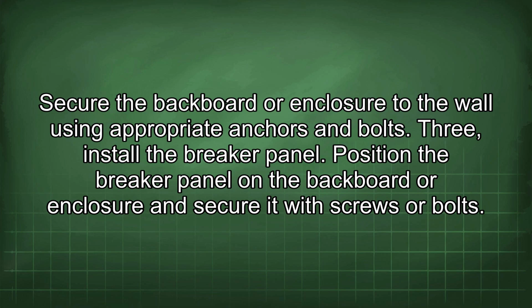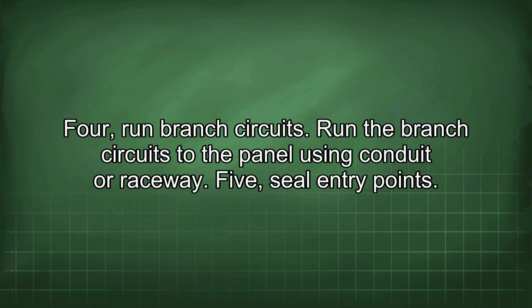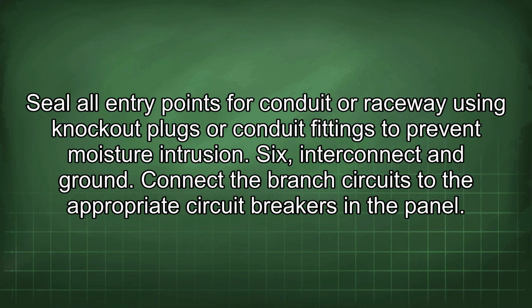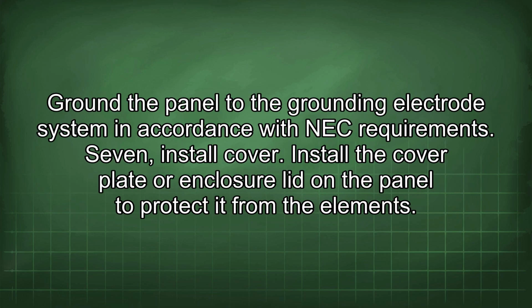3. Install the breaker panel. Position the breaker panel on the backboard or enclosure and secure it with screws or bolts. 4. Run branch circuits. Run the branch circuits to the panel using conduit or raceway. 5. Seal entry points. Seal all entry points for conduit or raceway using knockout plugs or conduit fittings to prevent moisture intrusion. 6. Interconnect and ground. Connect the branch circuits to the appropriate circuit breakers in the panel. Ground the panel to the grounding electrode system in accordance with NEC requirements. 7. Install cover. Install the cover plate or enclosure lid on the panel to protect it from the elements.